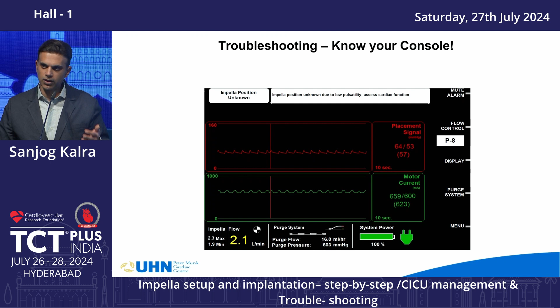So now when we look at the hemodynamics, we see same blood pressures, but now your CVP is 3. So what's the problem? This is a device that will suction when you're dry. And as a result, in this case, you have a suction alarm, where because you are either bleeding or you're too dry or you're vasodilated, the device cannot generate the flows that it's supposed to. And that is why your placement signal shows a low pressure. It's because you're not getting effective hemodynamic support. And this is the differential associated with that problem.